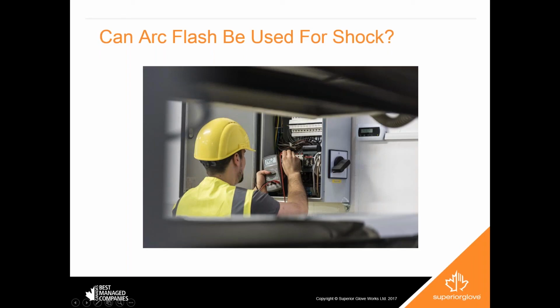Is there sort of a catch-all distance that you should be using when trying to avoid arc flash? Is there a specific distance? How is that going to work? Yeah, so unfortunately, it's not as easy as 10 feet away, you're always going to be safe. Depending on the machine, depending on the voltage that you're working with in that machine, that's going to play a big part in how far you need to be away from the machinery. But again, that standard, the IEEE 1584 will be able to help you calculate your boundaries.